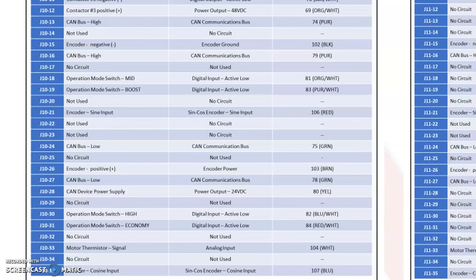28, this is a 24 volt output, and a lot of CAN communication accessories use 24 volts as their power supply. This actually powers the adapter when you plug it into the side of the machine to connect with the computer. Pin 30 is high speed. Pin 31 is the economy speed. Pin 33 is the temperature sensor input that comes up with the encoder wires. And then pin 35 is the cosine, so that's the other speed input. So we have the sine input and the cosine input. Those are used to control or read the speed of the generator.